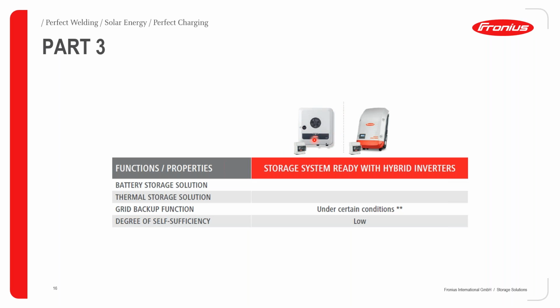Okay, just remember, in such a system, the Gen 24 Plus, when it's only installed with a smart meter, can offer you backup power on the PV point without any batteries. Okay, as long as you have enough PV being produced. So with the Gen 24 Plus range, we can offer 3 kilowatts of emergency backup power without batteries installed, as long as there is power being produced by your PV panels.